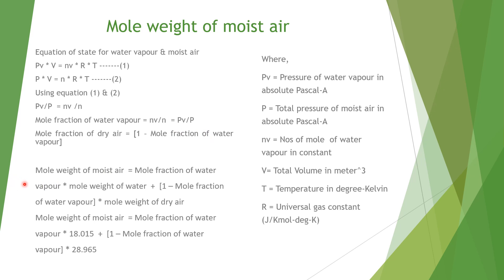The mole weight of moist air equals the mole fraction of water vapor times the mole weight of water vapor, plus the mole fraction of dry air times the mole weight of dry air. That is: mole weight of moist air = (mole fraction of water vapor × 18.015) + (1 minus mole fraction of water vapor) × 28.965. So if you know the mole fraction of water vapor, you can calculate the mole weight of moist air.